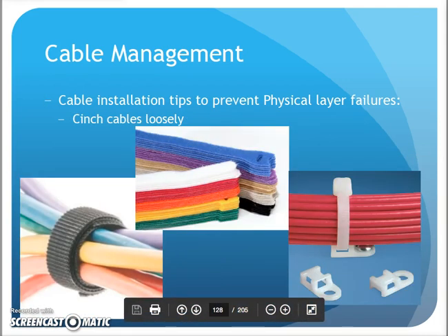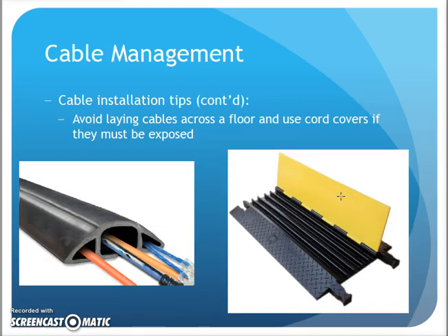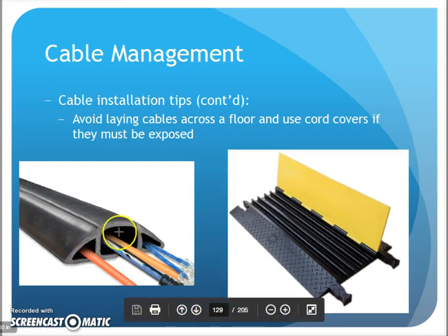Anytime I need to bundle my cables, I should be using, more times than not, these Velcro ties, and I'm bundling very loosely. If I use zip ties, these little plastic ties, I need to make sure they're loose so they do not cut into the insulation or cause that cable to get kinked or bent. I should avoid laying cables across the floor, but if I have to, I need to make sure they're in some kind of cover so they are not stepped on or rolled across with a chair, which would cut the cable.